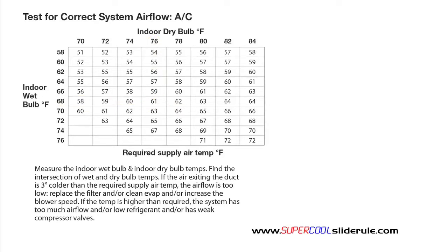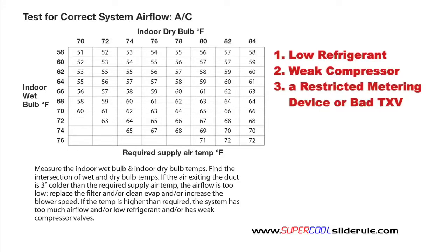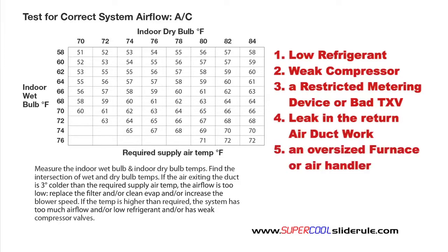If the actual tested temperature exiting the unit is more than 3 degrees higher than this, you could have several problems. The most common problems are: one, low refrigerant; two, a weak compressor; three, a restricted metering device or a bad TXV; four, a leak in the return ductwork; or five, an oversized furnace or air handler.